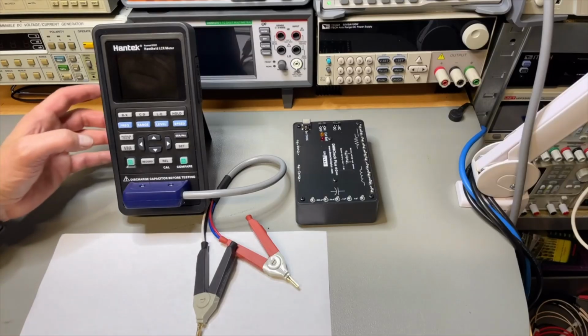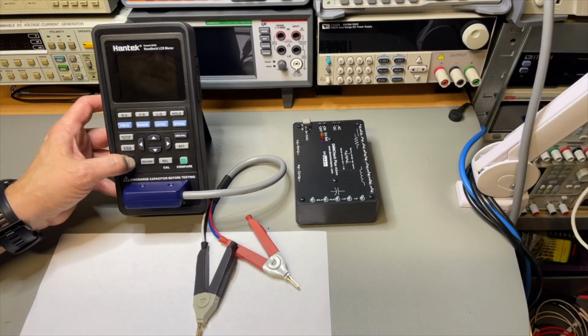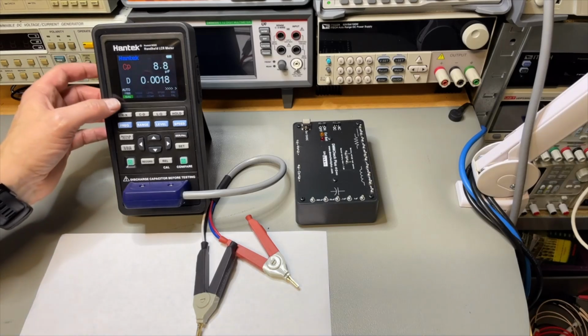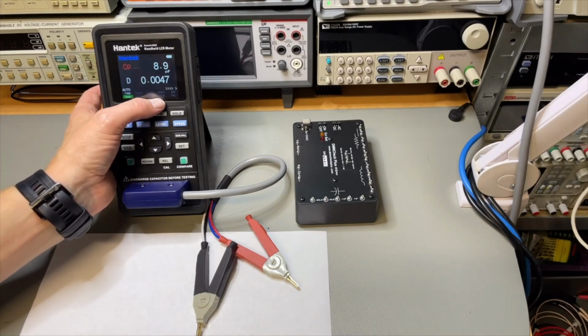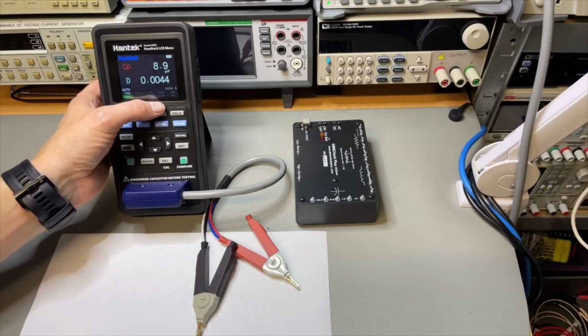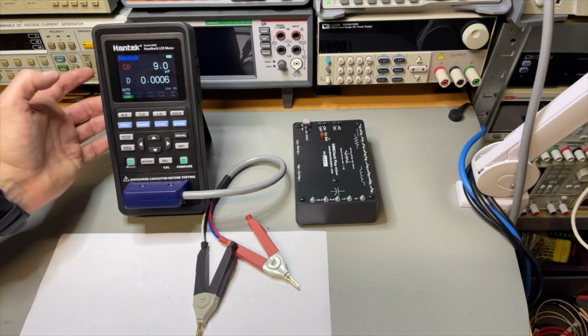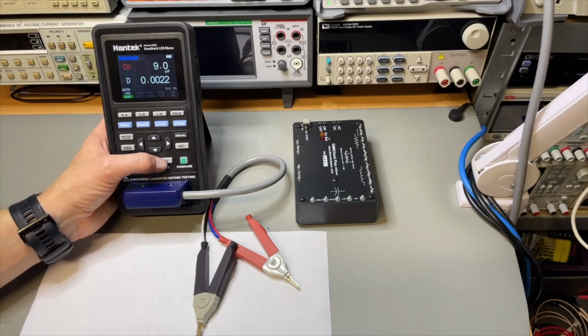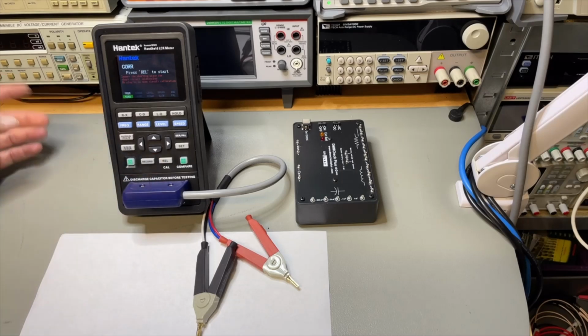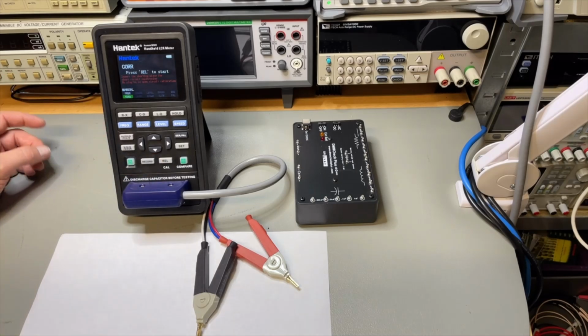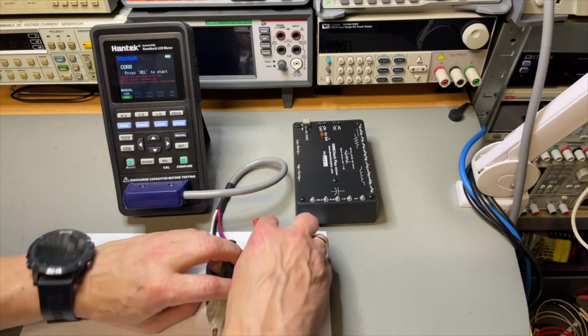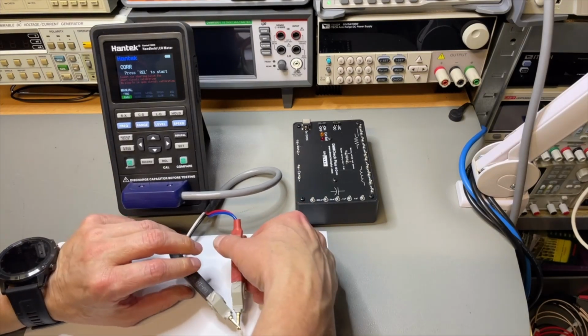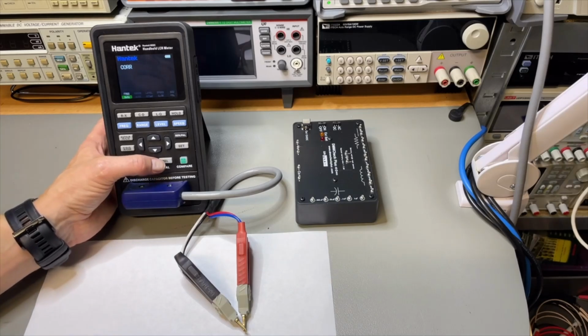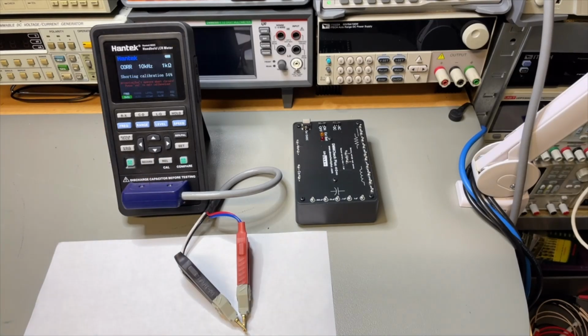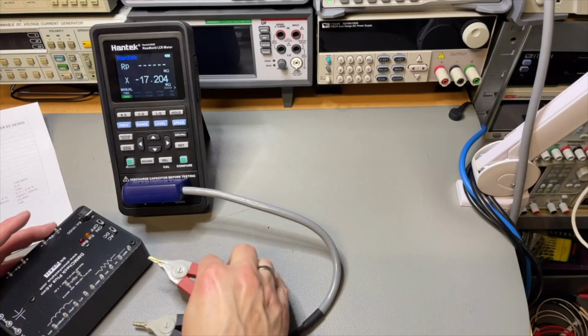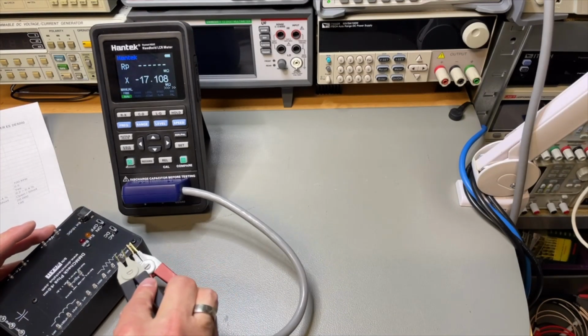Let's start with the open-close procedure. It is in auto mode, 1K, 600 millivolts. The speed is slow. That is okay because you get the highest accuracy. And it is now in parallel mode, so just leave it as it is. I think we need to push along the, yeah, it says insert the shorting. Well, we are not using the components directly, so I will short the connections like this, and we push the REL again. That was calibration for resistance, so let's just measure our resistors.